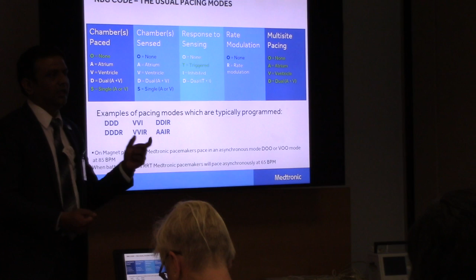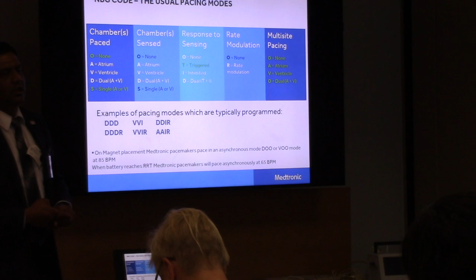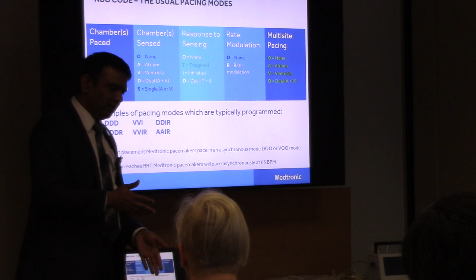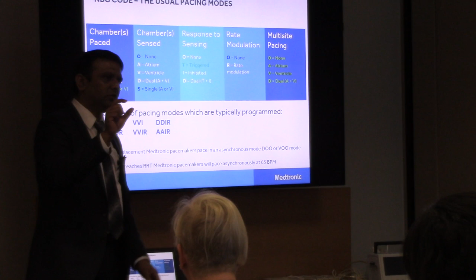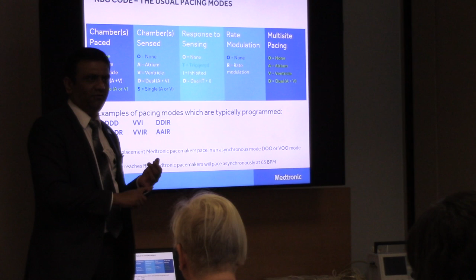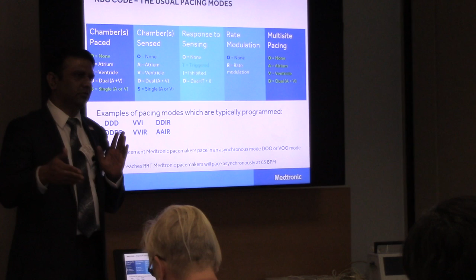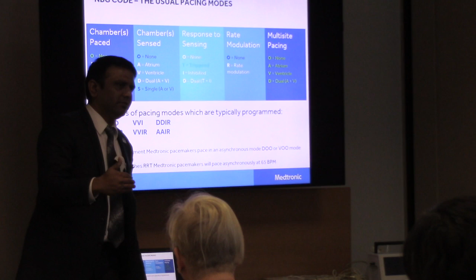And also, when you are in the DDD mode, there's another issue that comes into play called the AV delay. The AV delay is the time taken from the time you trigger the atrium to the time the ventricle is triggered. So there are two types of AV delays that you can program in any device. One is called a sensed AV delay. The other one is called a paced AV delay. That means if your atrium is paced, your AV delay would be a different number. So usually we set the paced AV delay to be higher than the sensed AV delay.